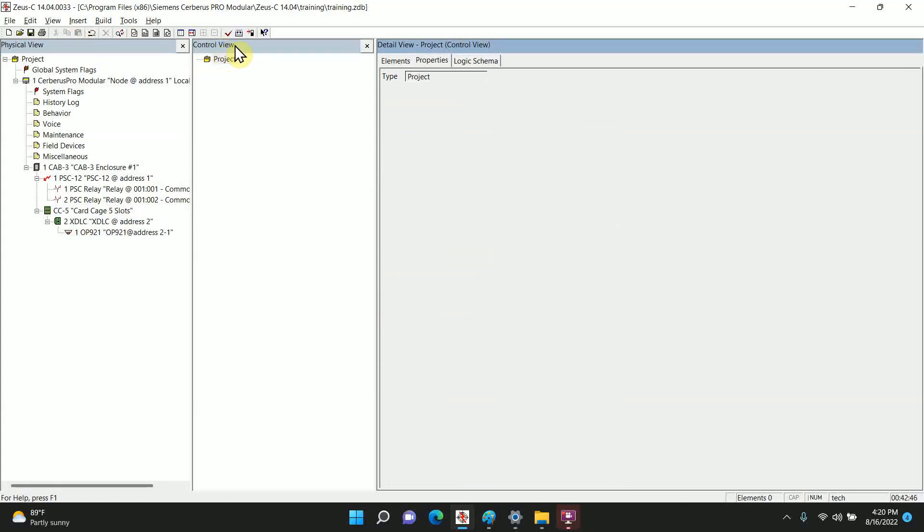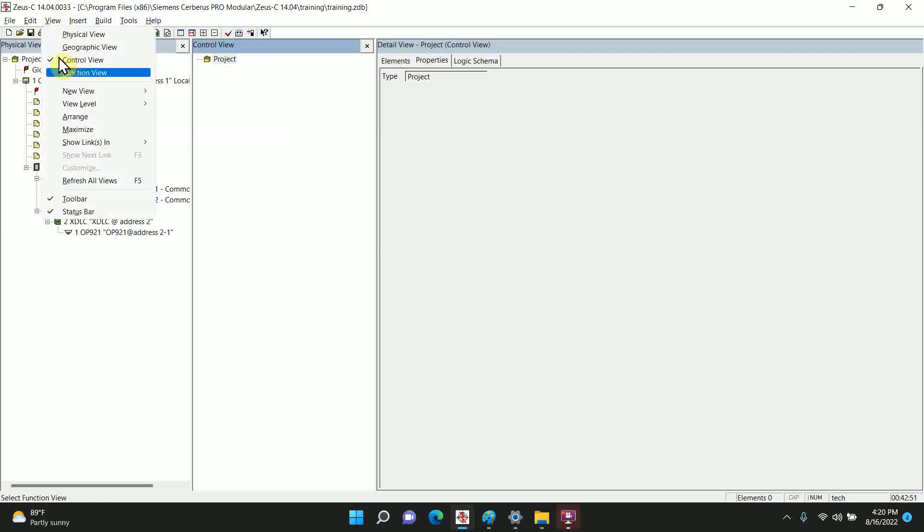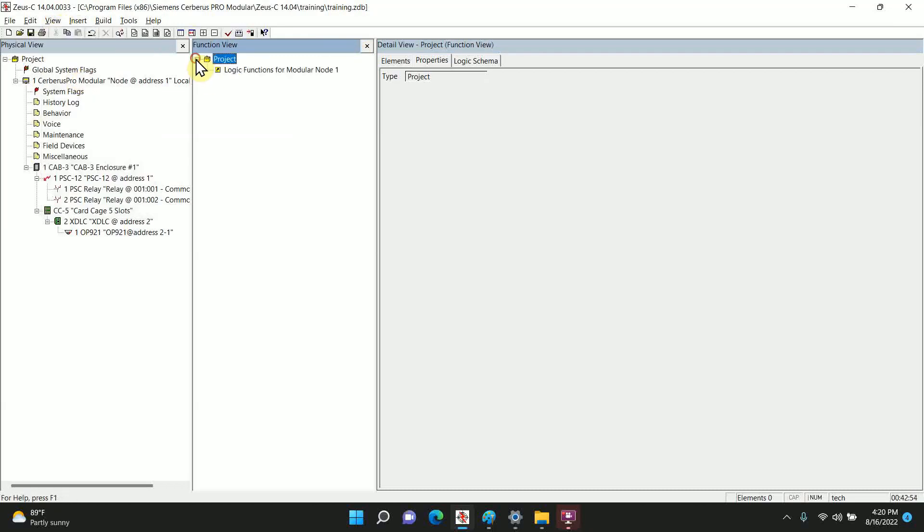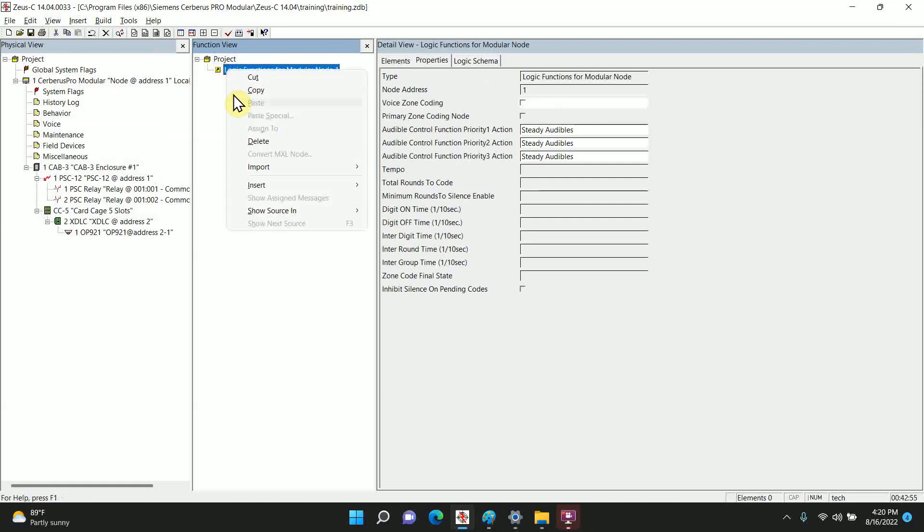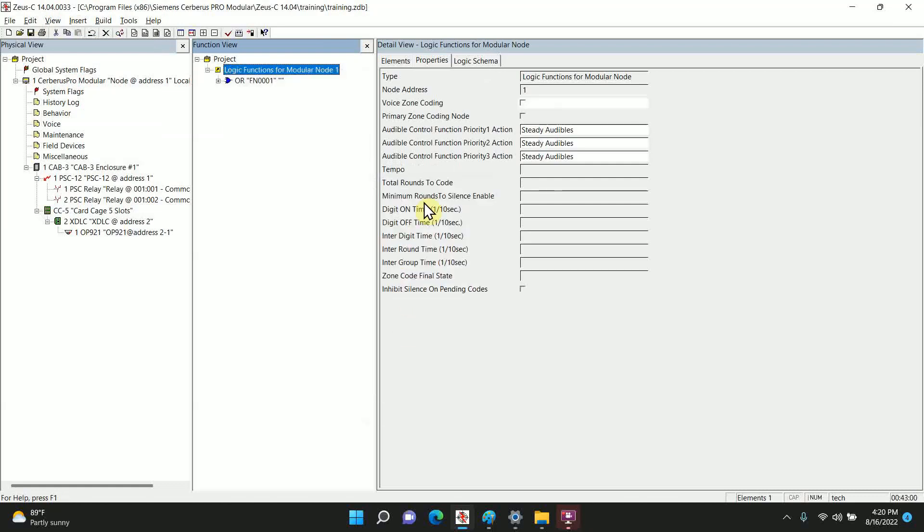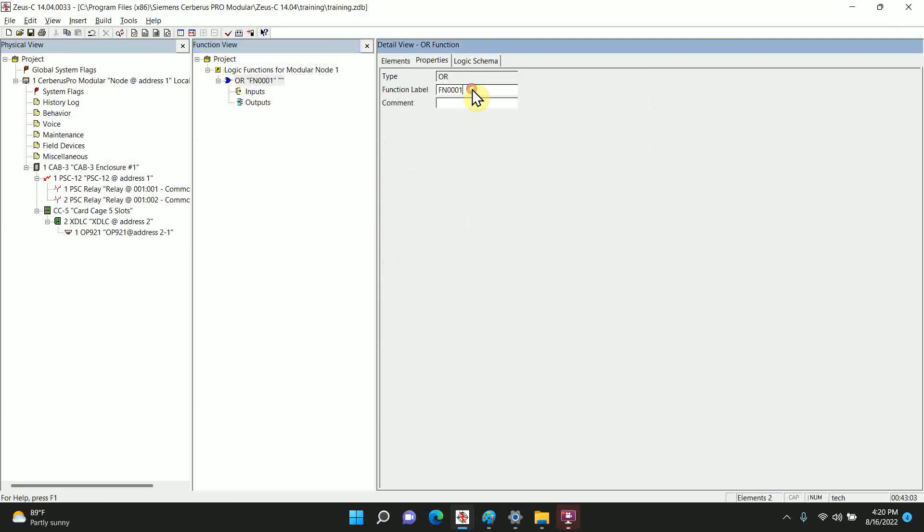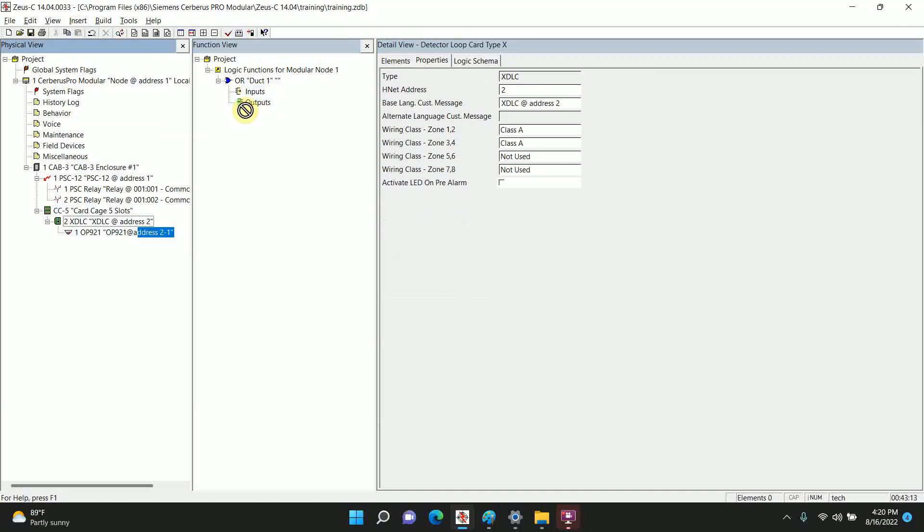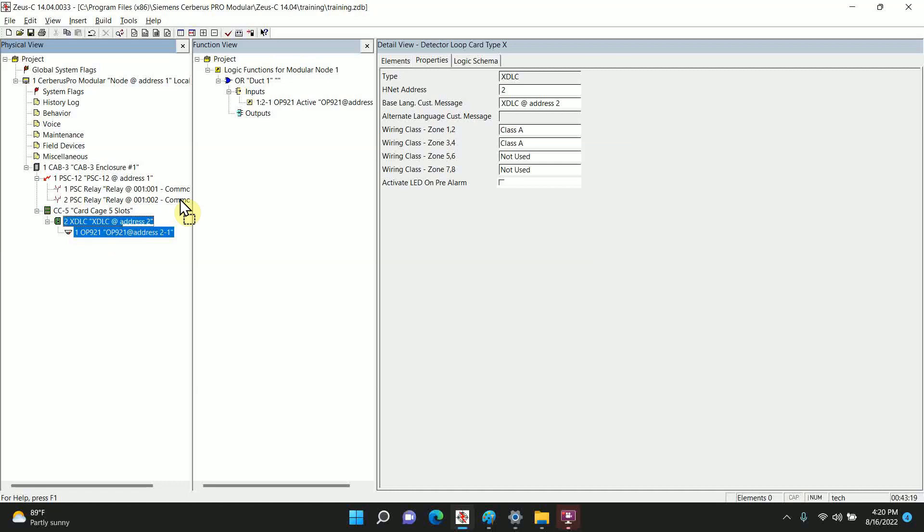So it has control view. It's a little misleading if it just came from the other ones because it's not a control. Instead of control, we need a function, so we're going to switch this to function view. We're going to add a function from node 1, insert, we're going to do an OR function. We'll name it duct 1. The input, what's going to cause this to trigger? We're going to drag the OP921 in the input. And for the output, we're actually going to drag the OP921 again. This is just referencing the output channel. And with that, the single duct detector will work.